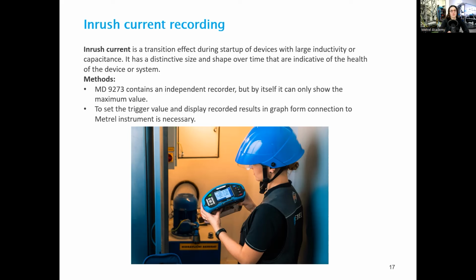We are talking about maybe 40 or 50 times the nominal value, but it only lasts a couple of milliseconds or even a couple of microseconds. The inductive and the capacitive effects can compound each other, and so we get a really, really high peak of current. Obviously, there needs to be some system in place to limit it. Otherwise, the whole circuit would have to be oversized to accommodate such a high startup current. So the measurement of inrush current will tell us about the health of the machine that we're measuring and about the health of its inrush limiting circuit.